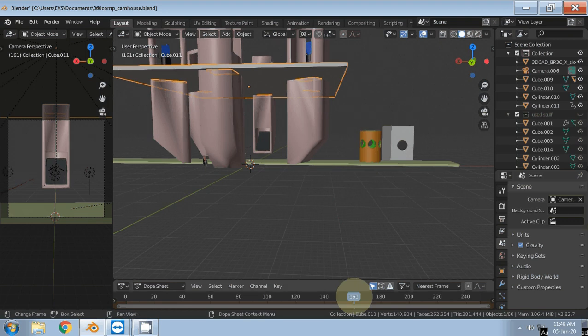So that means that if, for example, the can moves at 1 meter per second, maybe no problem. But if the can moves at 2 meters per second, that's quicker. Then maybe the machine is not able to know if the can is good. If the machine doesn't know if the can is good at that point, it will always reject it. So in that case, you will need to put the rejector further away. Well, if the can goes 1 meter, 1 meter 20 per second, the manual says that you can put the rejector at 60 centimeters away, 600 millimeters. That's a standard number.